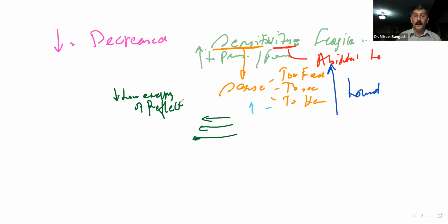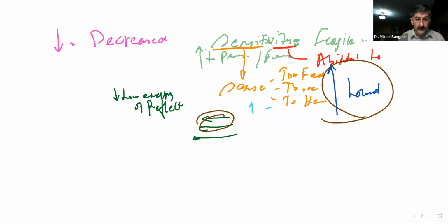And mainly, as I said, this is a consequence, or an effect, of your backing material: the transducer has a low or decreased sensitivity. That will mainly mean that it may not respond to low energy reflections, but only respond to very, very high energy reflections. These low energy reflections will not produce image information.